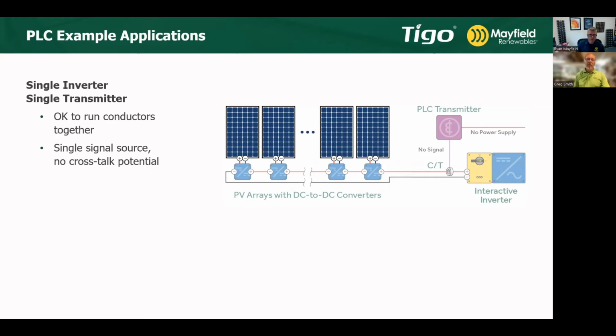Yeah, you hit it. Think of each one of those MLPEs as a normally open switch, and they need the signal from the PLC, which we call a keep alive signal. I keep wanting to call it a heartbeat, but it's a keep alive signal. As long as those MLPEs see that keep alive signal, they close their relay and allow the module voltage to flow through them. You connect the MLPE in series, so you've got full string voltage at that inverter if the PLC has power.